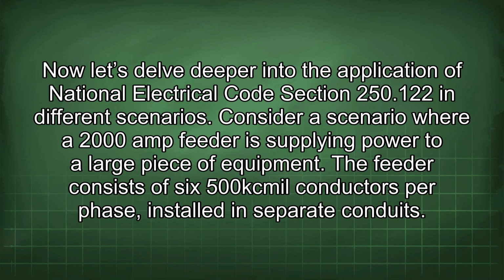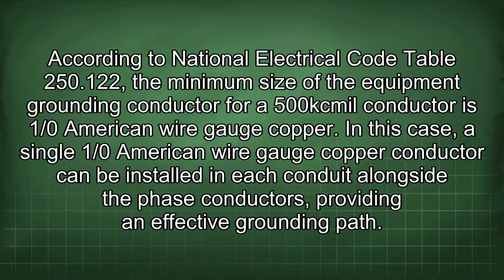Now let's delve deeper into the application of National Electrical Code Section 250.122 in different scenarios. Consider a scenario where a 2000 amp feeder is supplying power to a large piece of equipment. The feeder consists of 6 500kcmil conductors per phase installed in separate conduits. According to National Electrical Code Table 250.122, the minimum size of the equipment grounding conductor for a 500kcmil conductor is 1/0 American wire gauge copper. In this case, a single 1/0 American wire gauge copper conductor can be installed in each conduit alongside the phase conductors, providing an effective grounding path.